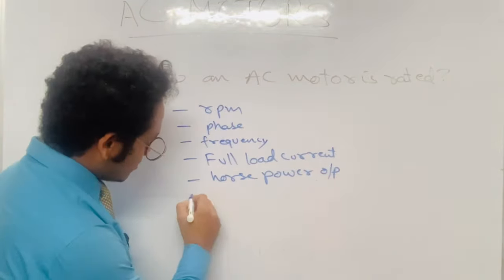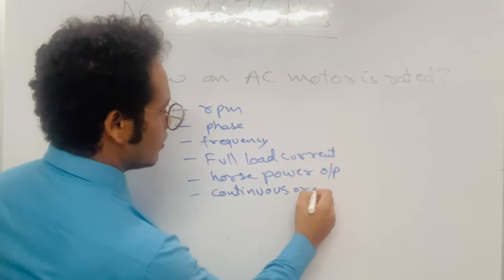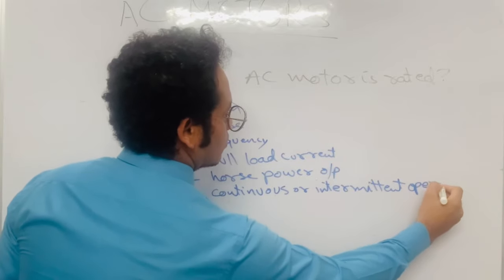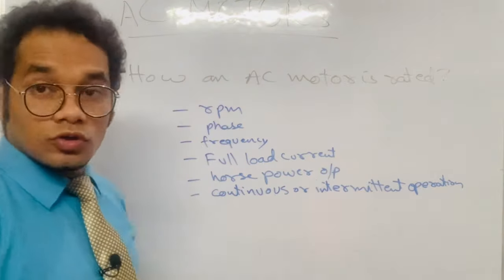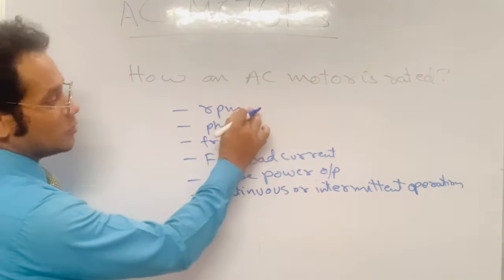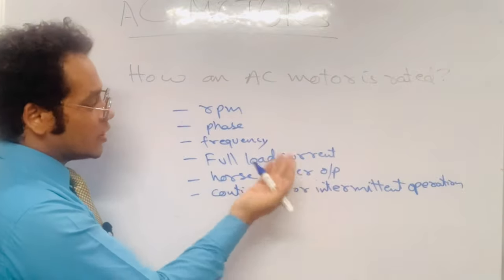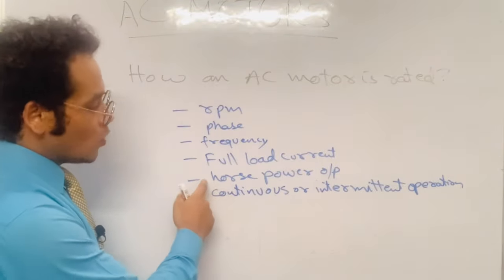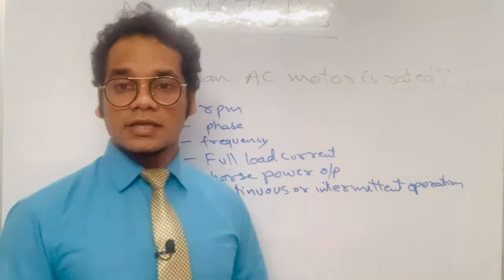Additional rating parameters include horsepower output — that is, how much horsepower is in the mechanical energy output of the motor — and whether it is designed for continuous or intermittent operation. So the parameters for rating an AC motor are: RPM, number of phases, frequency, full load current, horsepower output, and continuous or intermittent operation.